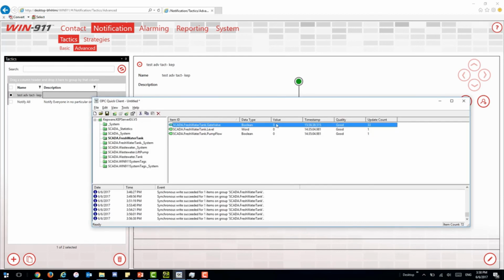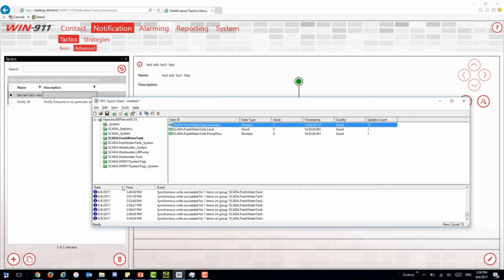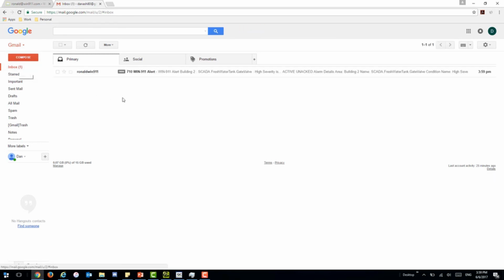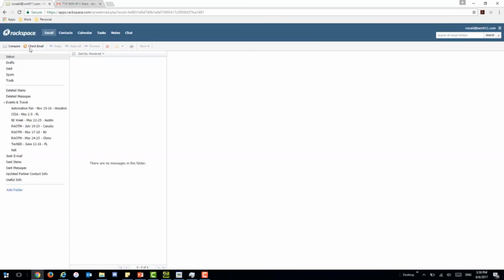Let's go ahead and set this off. All right, give it a quick second here. As you can see, the time it takes to get set off, or to notify, is very, very quick. So we have our notification to Dan, active and unacknowledged as it should be, showing the current severity there, and then we should not get any notification to this inbox, which we are not.